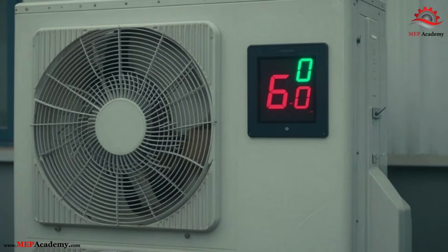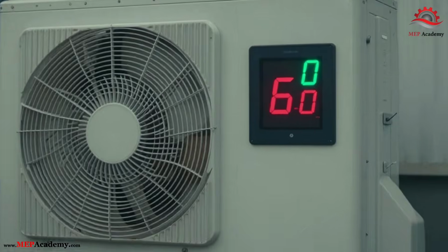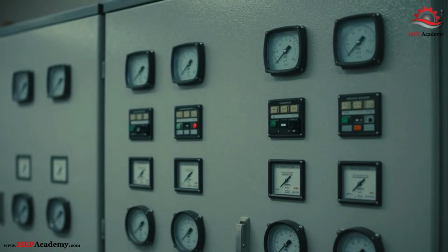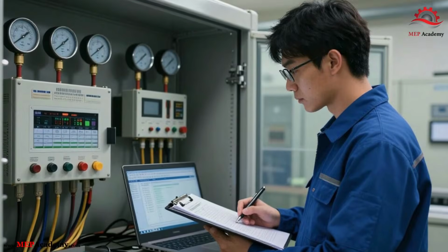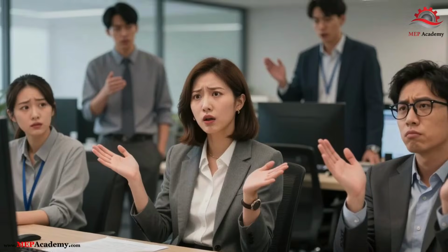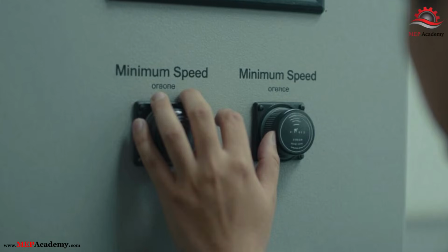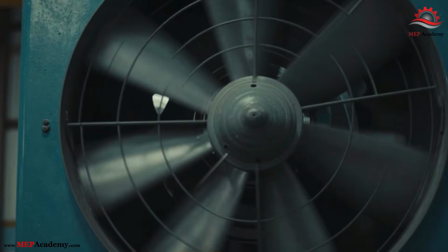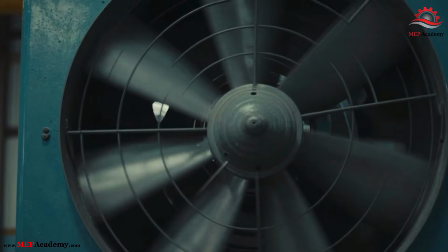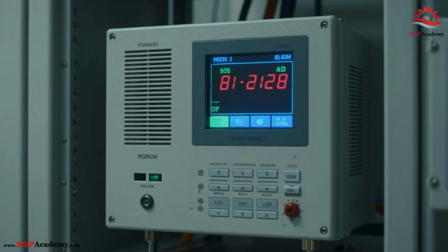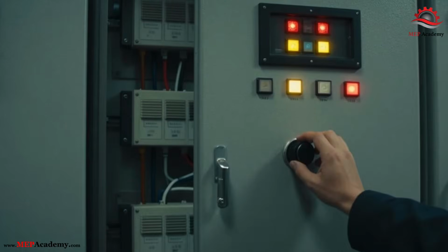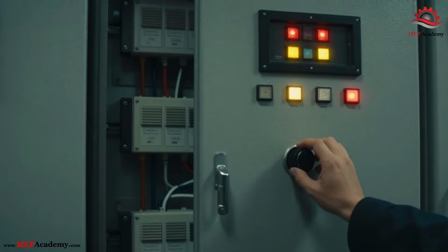Section 5. Why energy savings disappear. Here's what typically happens. The system is commissioned correctly. Occupants complain. Operators override minimum speeds. The fan slowly creeps back towards 60 Hz. 6 months later, the VFD is running, but savings are gone. Energy retrofits only work if the control strategy survives turnover.